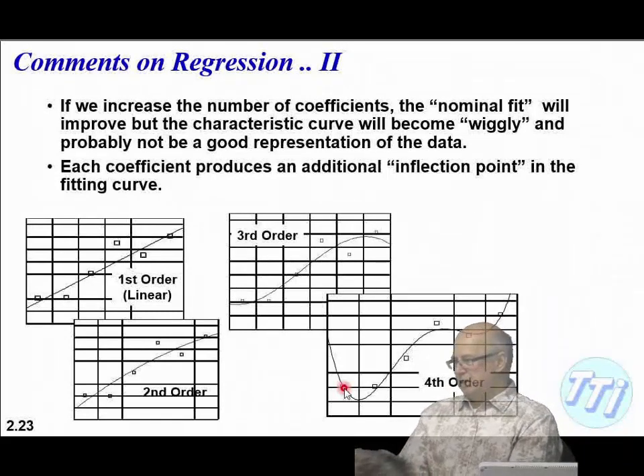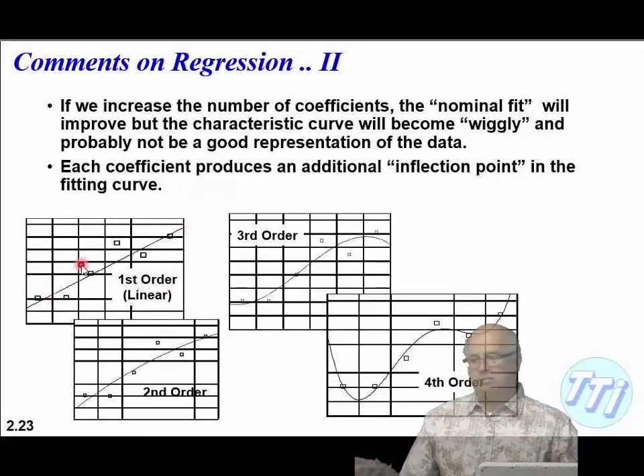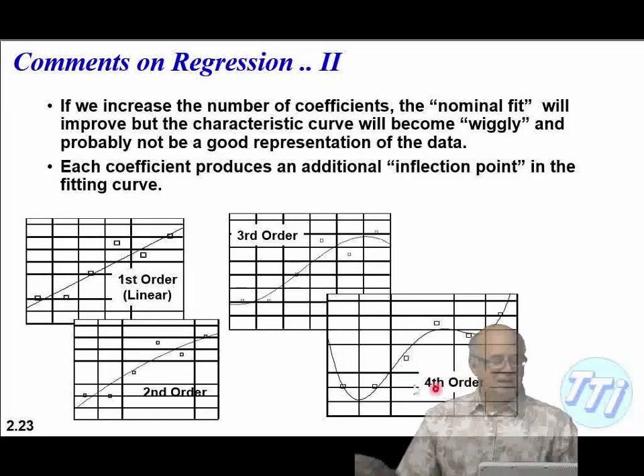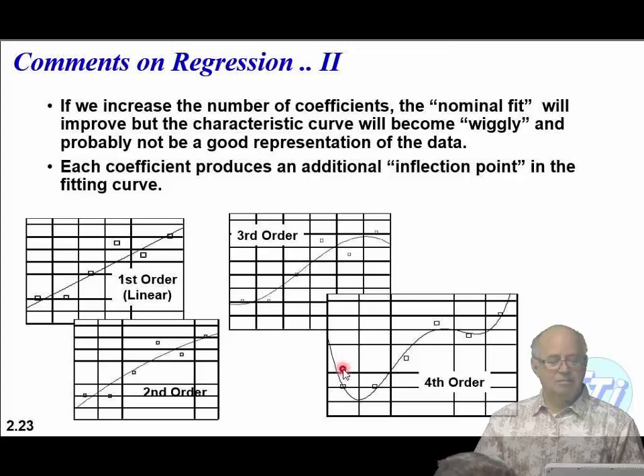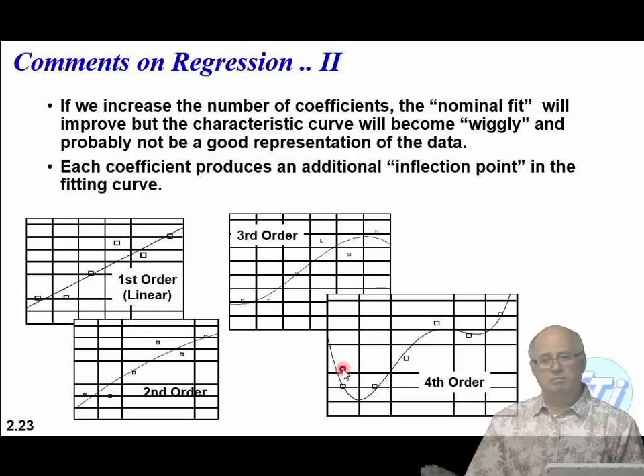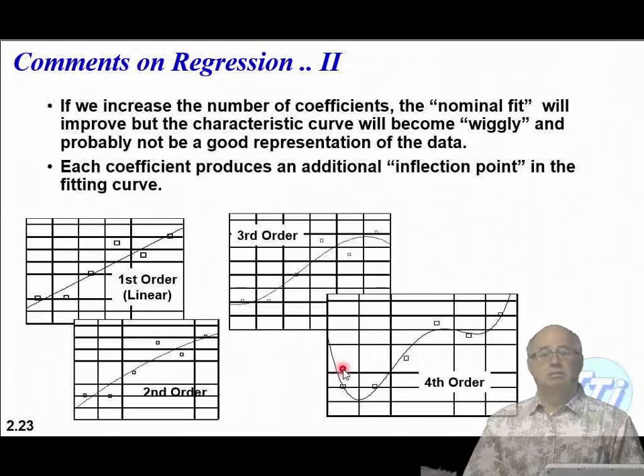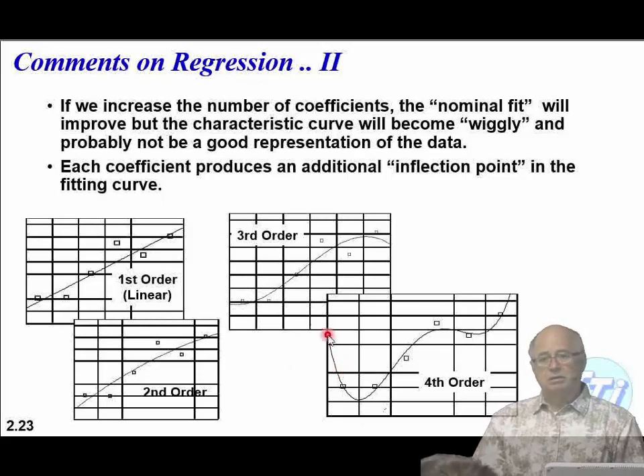That also highlights extrapolation dangers. When you buy strain gauges — even STC-matched ones from manufacturers like Vishay — they give you a fifth-order polynomial for temperature compensation, but they specifically tell you not to extrapolate outside the given temperature range. There's a good fit in the middle of the range, but outside of it you're on your own. That's a great real-world example.